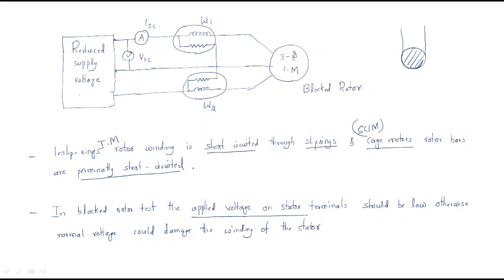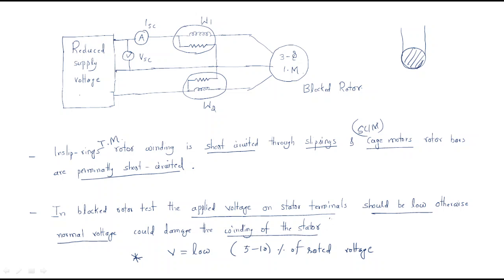In the block rotor test, the applied voltage on the stator terminals should be low — only 5 to 10% of the rated voltage. This is very important; otherwise, if you apply normal voltage it could damage the stator winding.